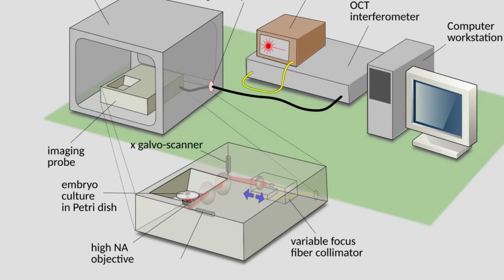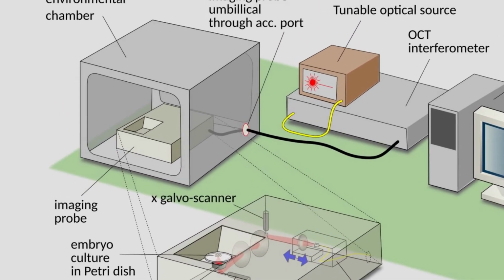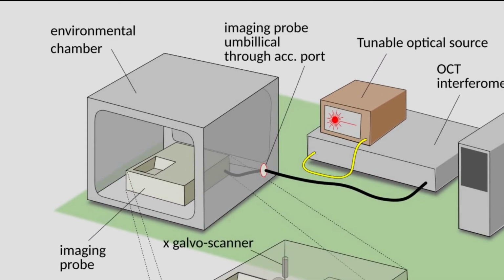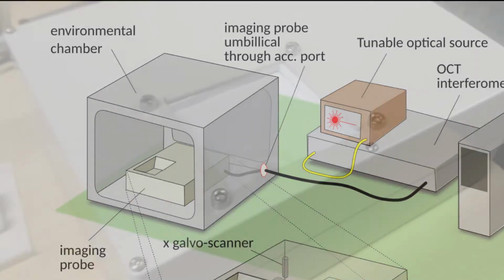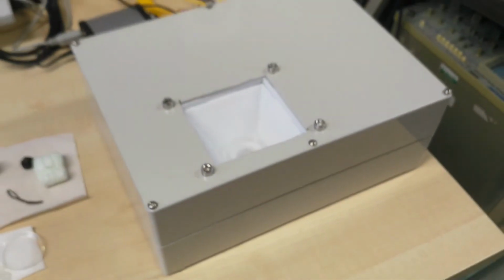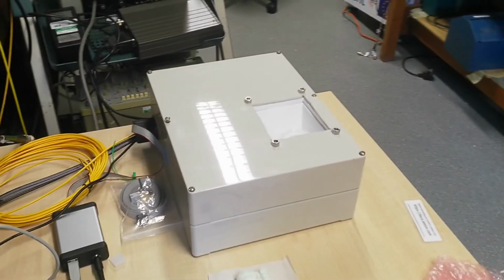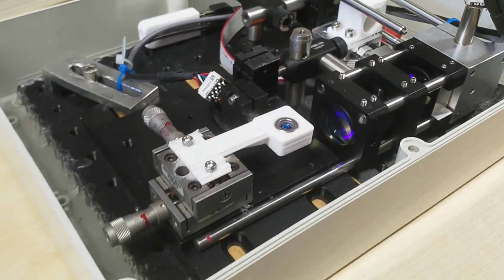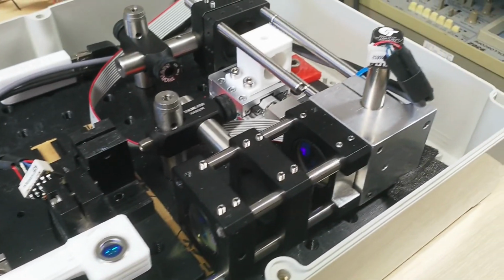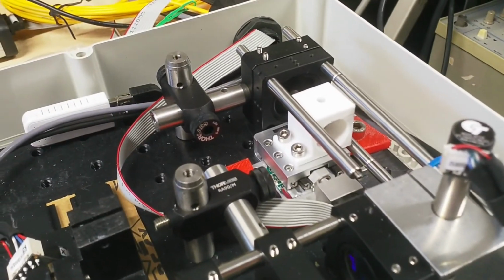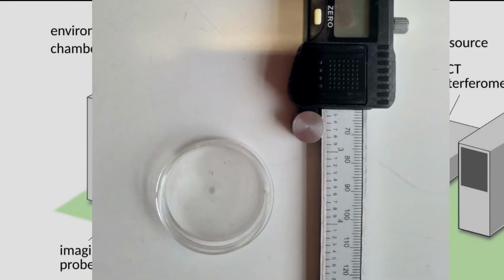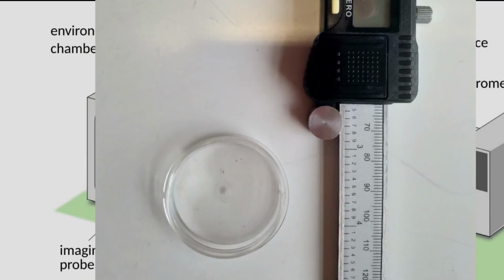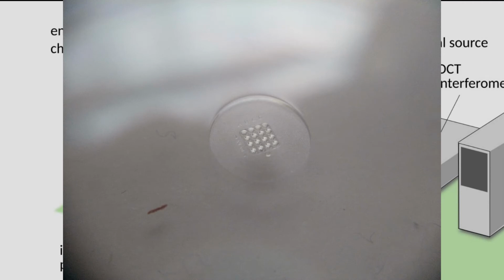Currently, we are developing an OCT imaging probe which can be introduced into an environmental chamber. This environmental chamber presents control over temperature, humidity, and gas ratios, and the probe itself is a high-resolution imaging probe with a lateral resolution of 2 to 4 microns, with remote focus adjustment, and an imaging interface dimensioned for specialist Petri imaging dishes.